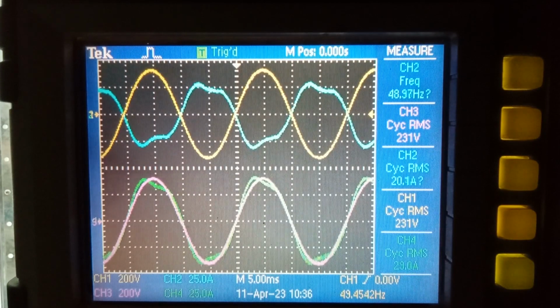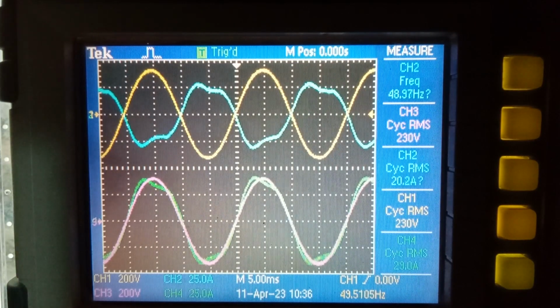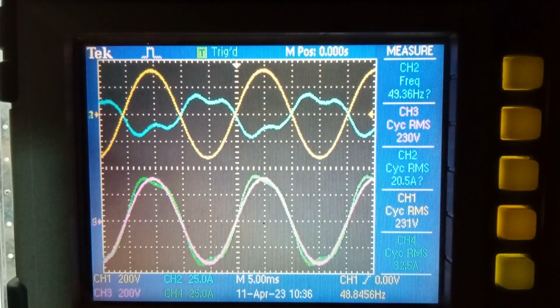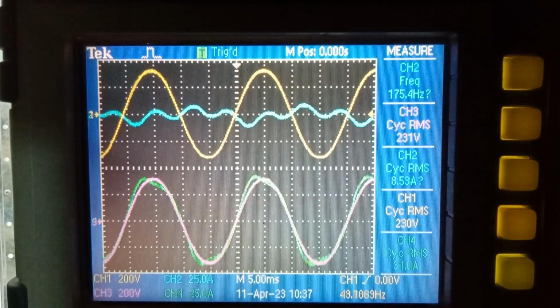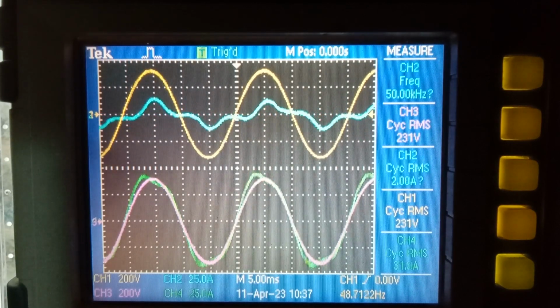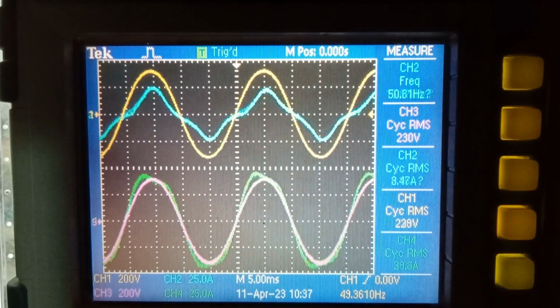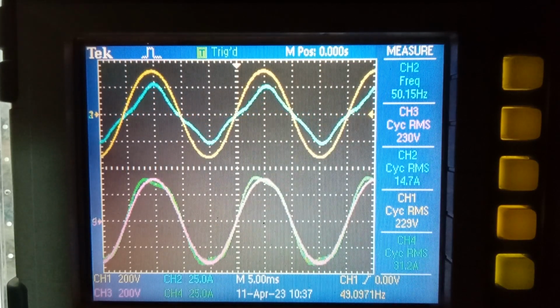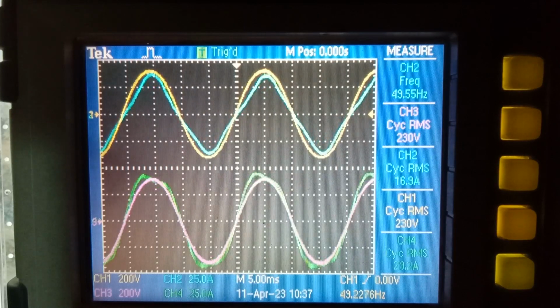As we change the load on the system, the inverter will adjust the current that it draws to keep the current out of the generator constant. So if we increase the load on the system, the inverter will supply more current, but the generator will keep supplying the same current.